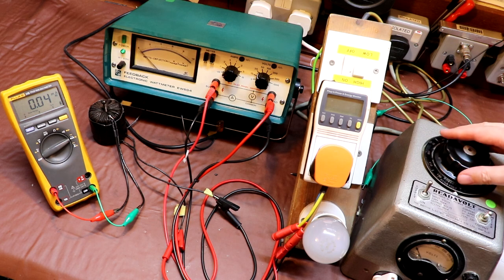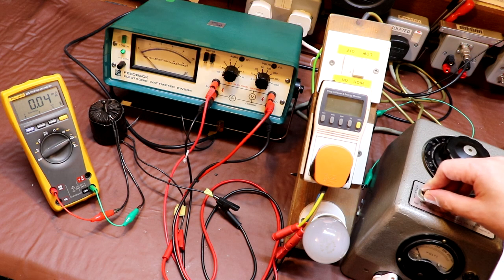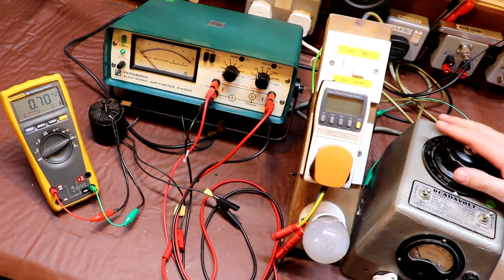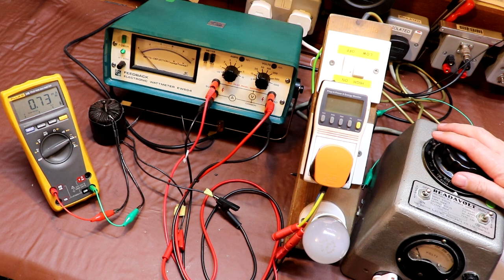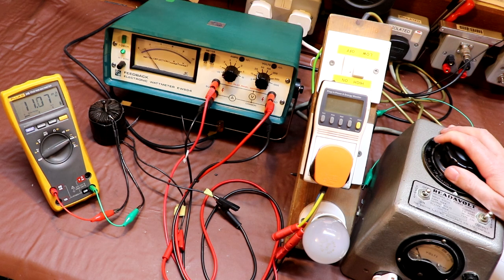So after first checking that our variac has been turned fully down, we can switch on. And we're now going to very carefully turn up the variac until the secondary current measures 20 milliamps. Remember, we're using 20 milliamps because that's what the transformer specification said the rated output was. I'm only turning this up a little. I suspect we've only got a few volts across the primary of the transformer. It doesn't take a lot of voltage to induce a secondary current of 20 milliamps, so I'm really being careful.